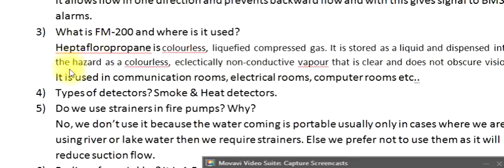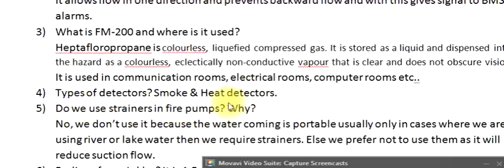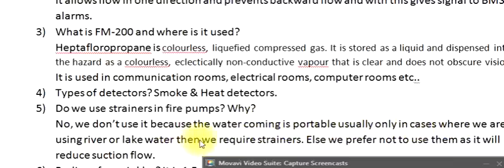Question 4: Types of detectors? Smoke and heat detectors. Question 5: Do we use strainers in fire pumps? No, we don't use them because the water coming in is potable. Usually only in cases where we are using river or lake water do we require strainers. Otherwise we prefer not to use them as they will reduce suction flow.